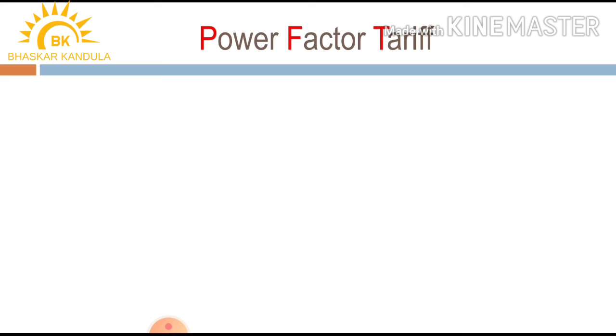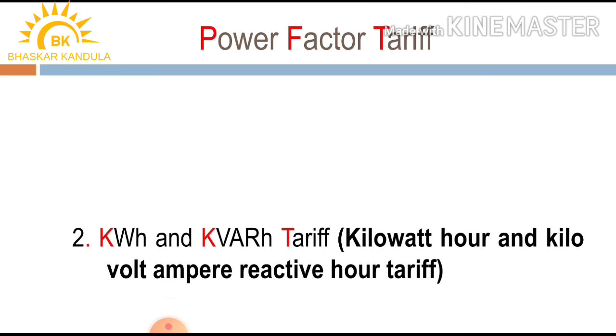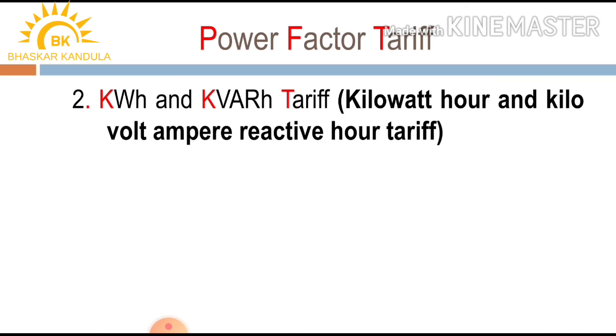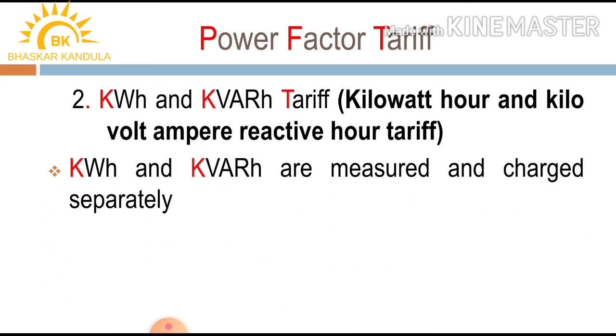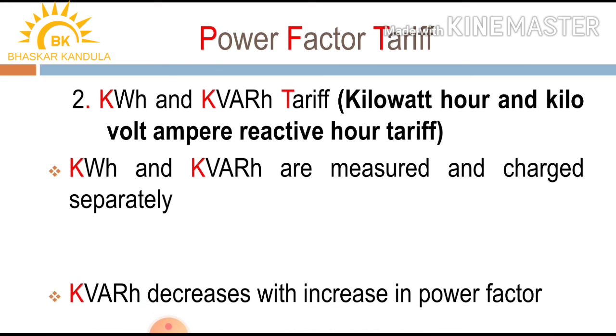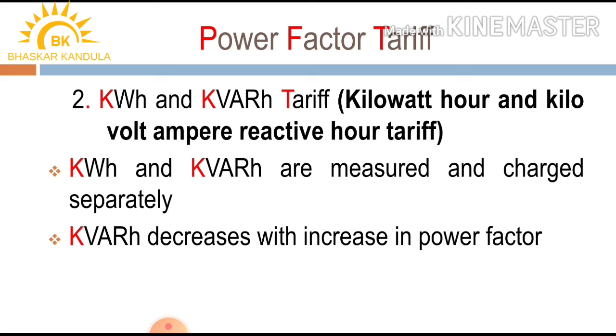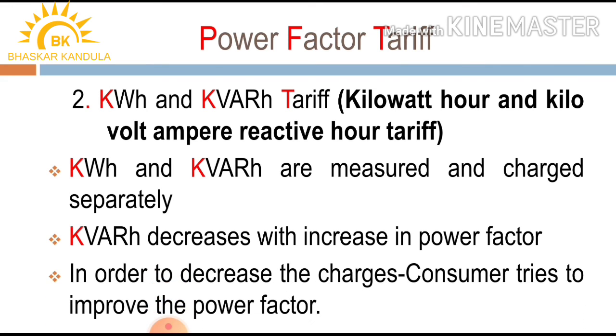In the kilowatt hour and kilo volt ampere reactive hour tariff, both kilowatt hour and kilo volt ampere reactive hour are measured and charged separately. Since kilo volt ampere reactive hour decreases with an increase in power factor, the consumer is motivated to improve the power factor of their installation in order to decrease the charges on account of kilo volt ampere reactive hour recorded.